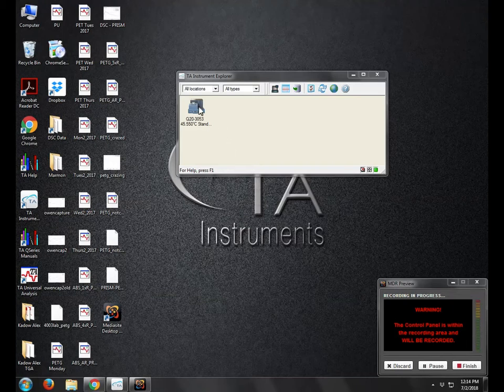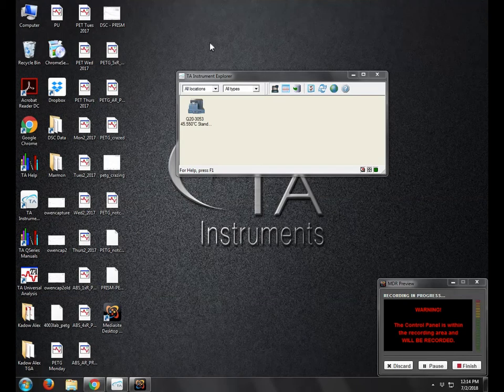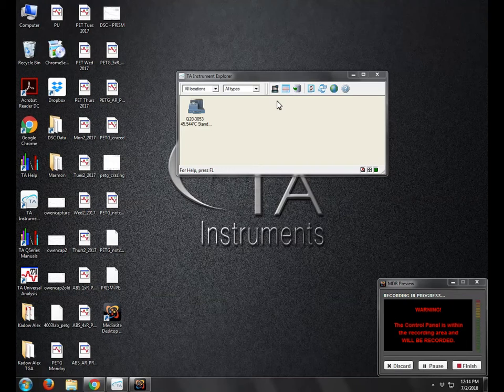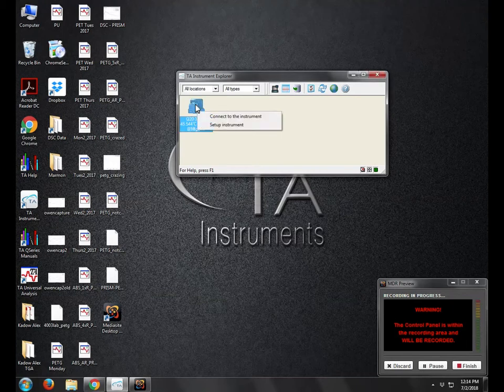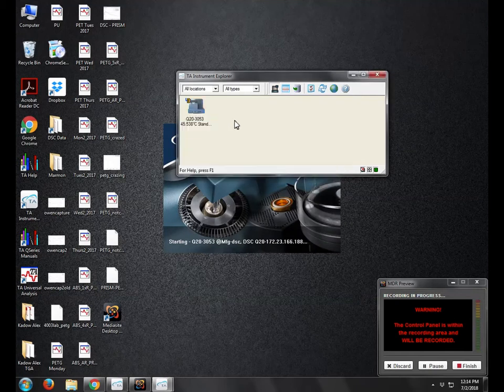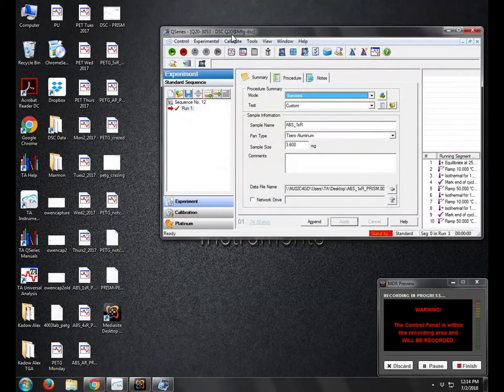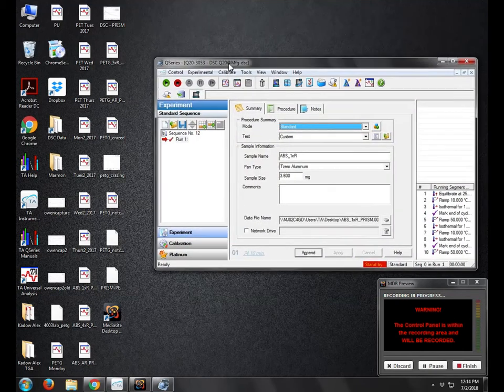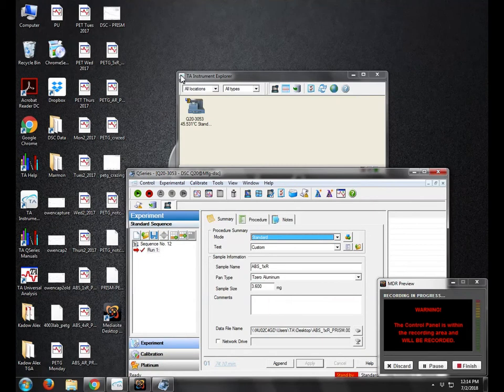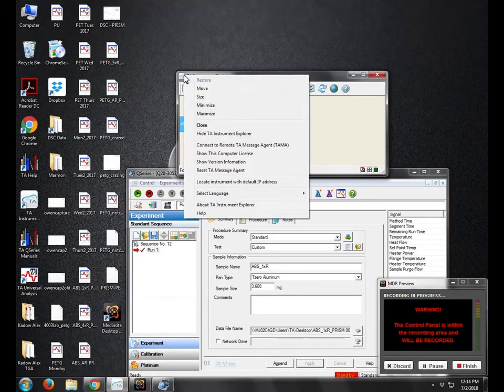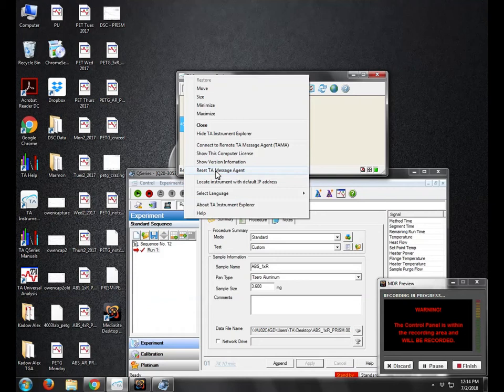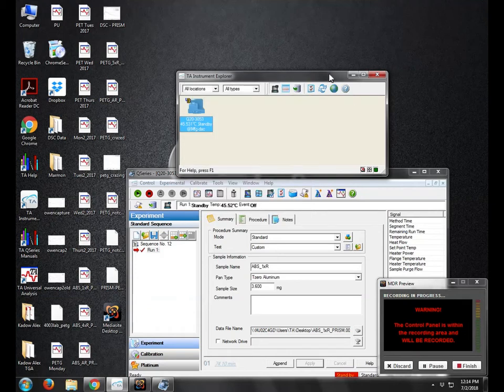If we open this TA Instrument Explorer, then we should see this icon. If you get an error when you right-click and connect to this instrument, then what you should do is click on this icon and click Reset TA Message Agent, and then hopefully you'll see it after that.